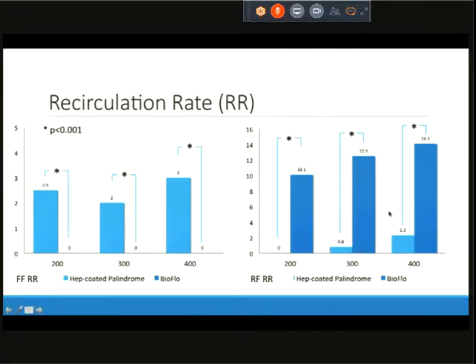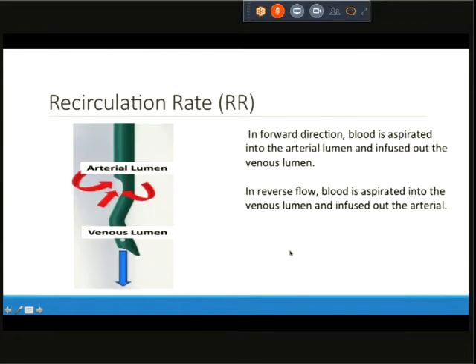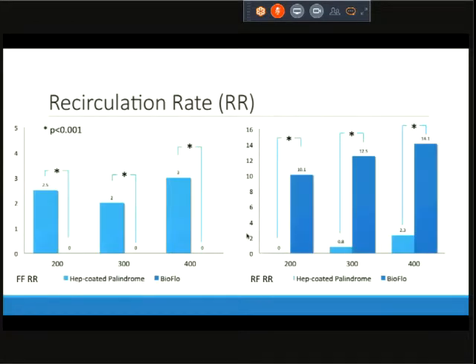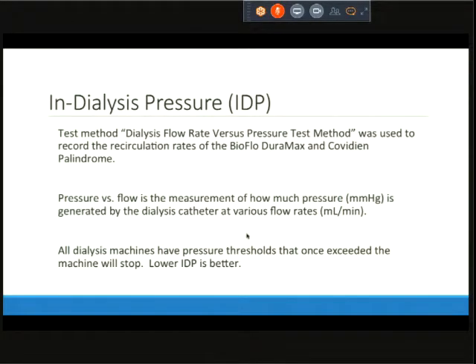However, if you look at the reverse flow, it completely changes the schematics, as you can see, with the BioFlo having a significantly higher recirculation rate compared to the heparin-coated palindrome, which is due to the design of the arterial lumen before the venous lumen, where, if it's reversed, anything that's released out of our arterial lumen can get aspirated by the venous lumen, and that's the reason why it has a higher recirculation rate compared to the other catheter.